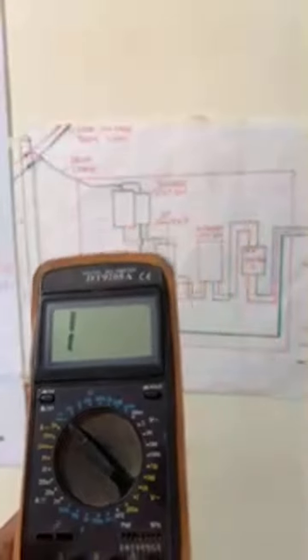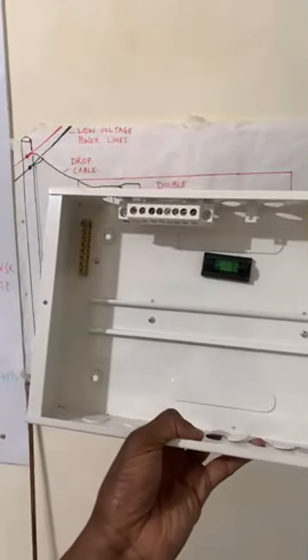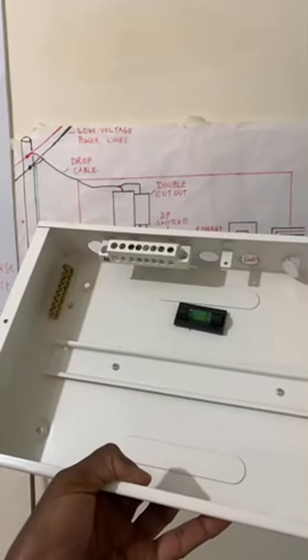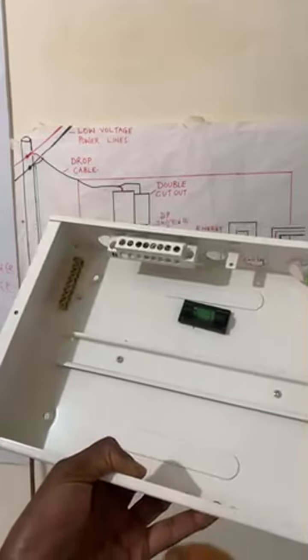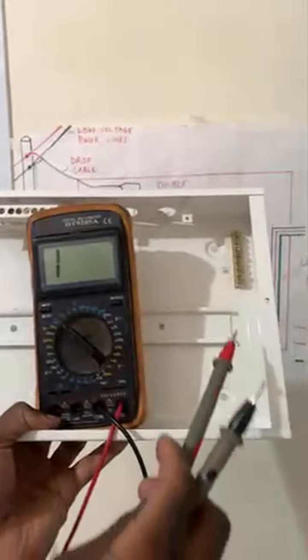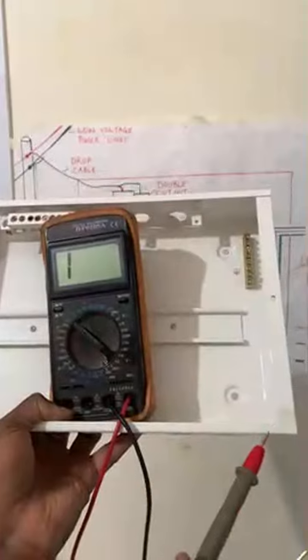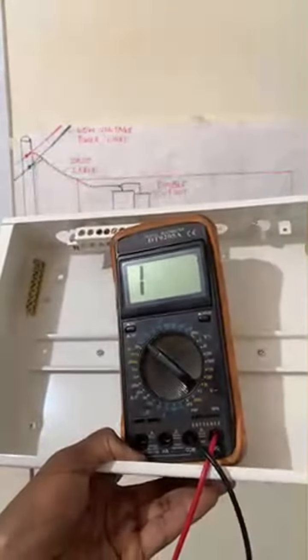So we'll turn our pointer all the way to that point, whereby if our probes come in contact, that means continuity. It simply means that the circuit or the connection is continuing, right? For our consumer unit here, we want to test: does that neutral bar have any relationship with the earth connection? Let us check. We will also check between these two earth bars on the side. Do they have contact, so that we can detect that indeed that box is well earthed?